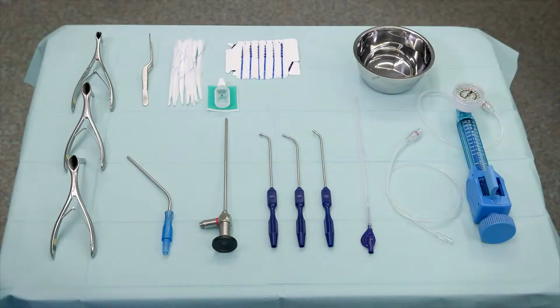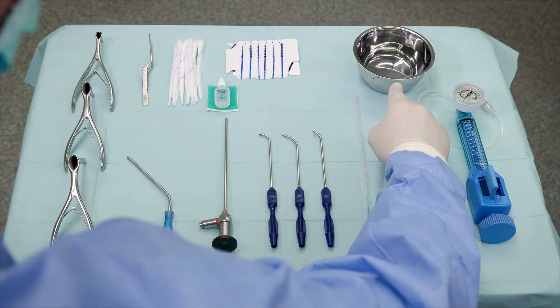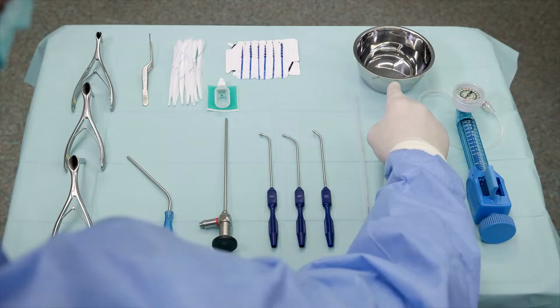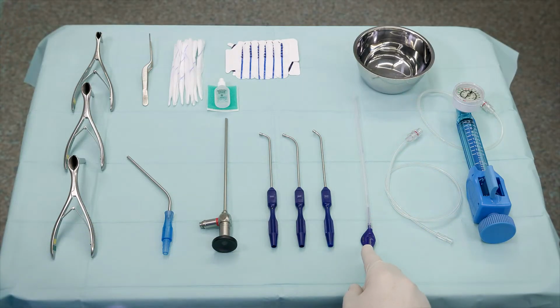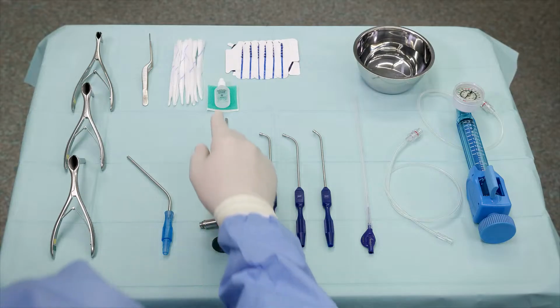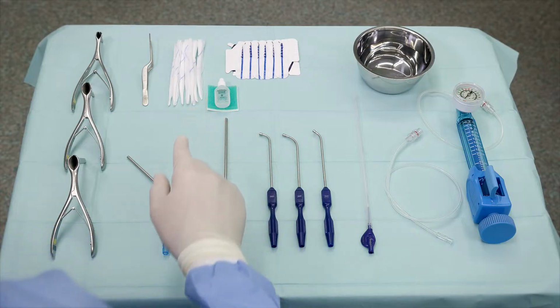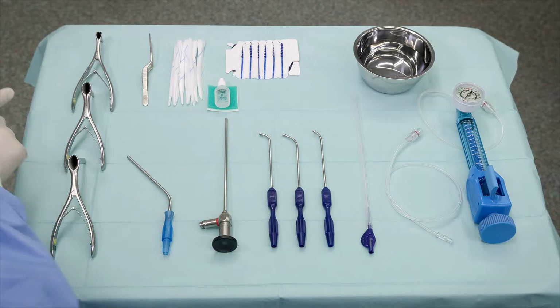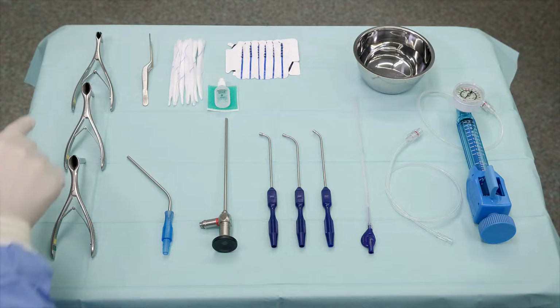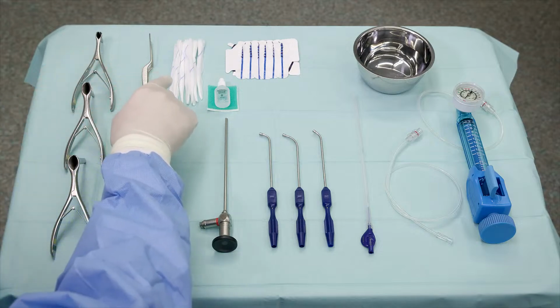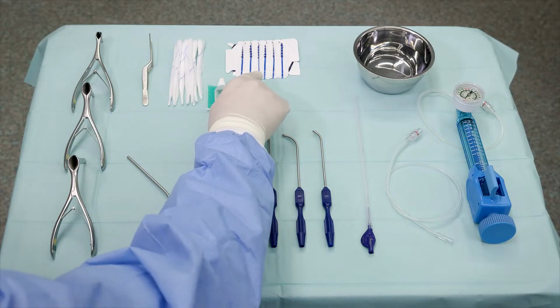Here we have a typical arrangement of the materials needed for the operative procedure. The inflation device with an extension tube. A bowl filled with sterile isotonic saline solution, NaCl 0.9%, and/or contrast medium. In this case, we used a TuboVent short balloon catheter. The TuboInsert insertion device. A rigid endoscope, usually with a 30 or 45 degree angle. Antifog solution for the endoscope. A suction tube. Various sizes of nasal specula. Dressing forceps for inserting swabs or patties, saturated in a decongestant medication solution.